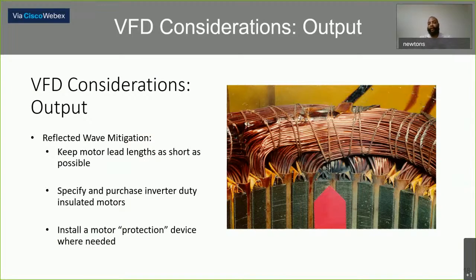This motor is designed for a certain voltage that it can sustain. We'll show this in another graph, but if the motor is not an inverter duty rated motor, it's expecting PWM, pulse width modulation, DC voltage turning on and off, and that voltage, as we saw in the graph before, that DC bus was around 650 volts. If we double that, that's around 1300 volts. So if you have a motor that has insulation rated for 1000 volts or 600 volts, that will give you issues. So it's important to keep your motor lead length short so you won't have to deal with reflective wave issues.